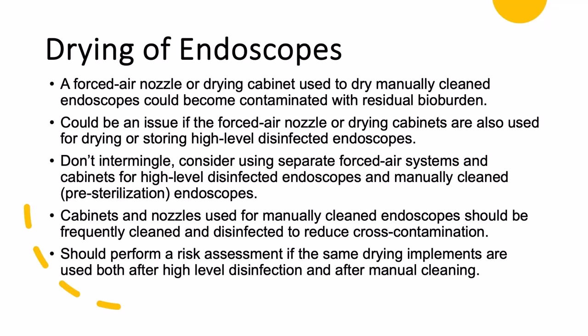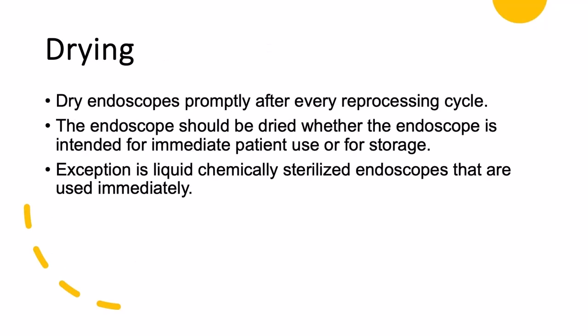Consider using a separate forced air system and cabinets for high-level disinfected endoscopes and manually cleaned endoscopes before sterilization. The cabinets and nozzles used for manually cleaned endoscopes should be frequently cleaned and disinfected according to the IFU to reduce cross-contamination. And if you're going to do this, where you have both types of scopes in your cabinet, you should perform a risk assessment if the same drying implements are used both after high-level disinfection and after manual cleaning. Dry your endoscopes promptly after every reprocessing cycle. The scope should be dried whether the endoscope is intended for immediate patient use or for storage, and the exception is liquid chemically sterilized endoscopes that are used immediately.